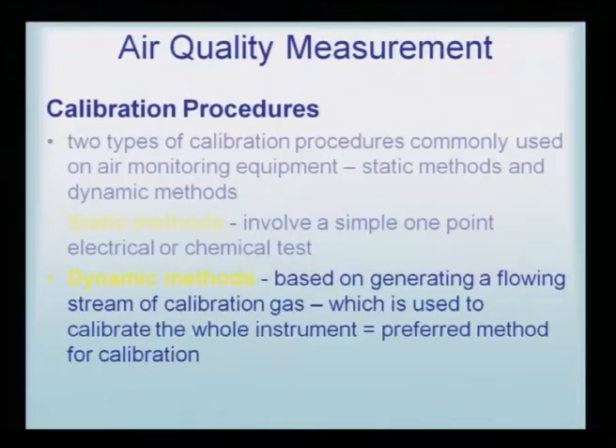The next method is the dynamic method, based on generating a flowing stream of calibration gas, which is used to calibrate the whole instrument, and that is the preferred method for calibration. So, a dynamic method is definitely having an edge over the static method. A static method, we can always say, is more qualitative, but the dynamic method is quantitative in its data.